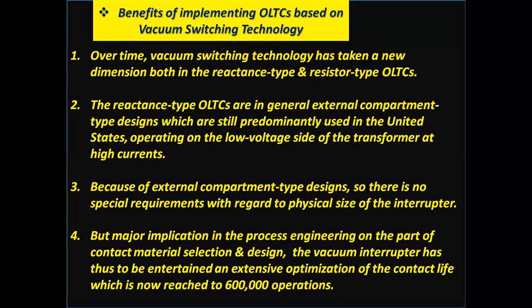But the major implication is in the process engineering on the part of the contact material selection and design. The vacuum interrupter has thus had an extensive optimization of the contact life, which has now reached 6 lakh operations.